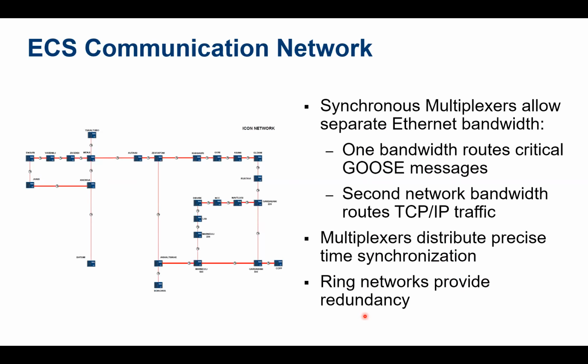Since we are keeping these two systems separate and we have separate communication networks for them, we decided so. Our intent was to keep these two systems as separate as possible. Since we have our communication network for ECS and for other protection degree systems, this was one more additional reason not to combine it with the SCADA system. Therefore, we have separate communication, and we have separate HMI for SCADA and for ECS systems.